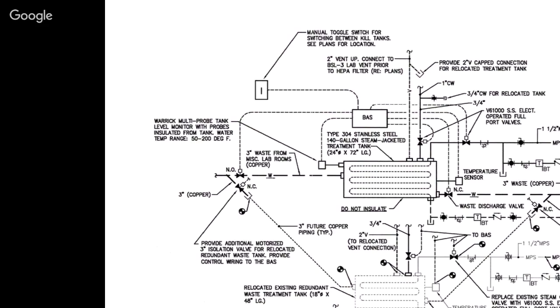You can see how complicated it is. There's always going to be a lesson learned. There's always something that goes wrong. So the thing that went wrong on this was this vent pipe was a copper pipe. It went up to the interstitial space. And on this project, we allowed PVC piping for the rest of the vent piping in the building. And that vent piping was exposed in the BSL-3, because previous projects were copper, and copper inhibits the activity of VHP for decoms. So on that project, we said all PVC. Well, we connected the copper pipe to a PVC pipe up in the interstitial space.